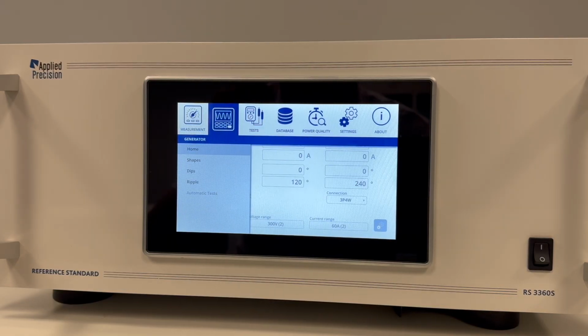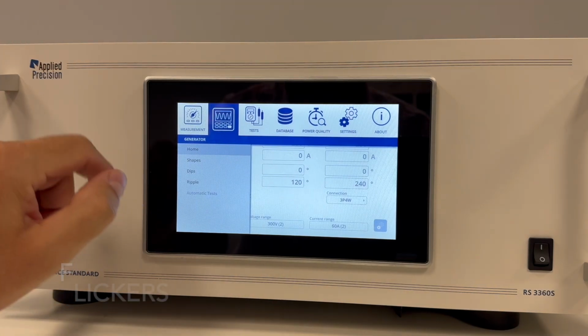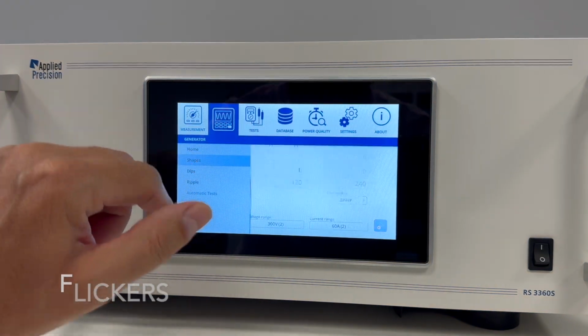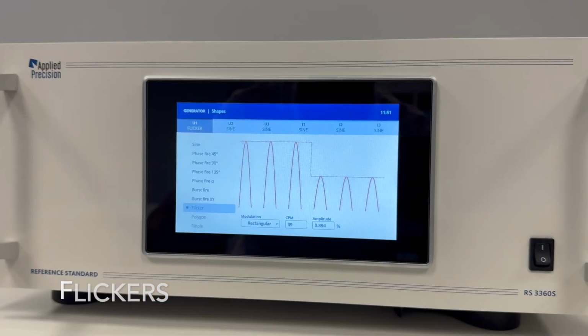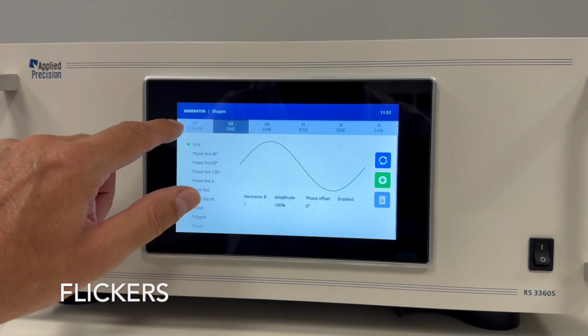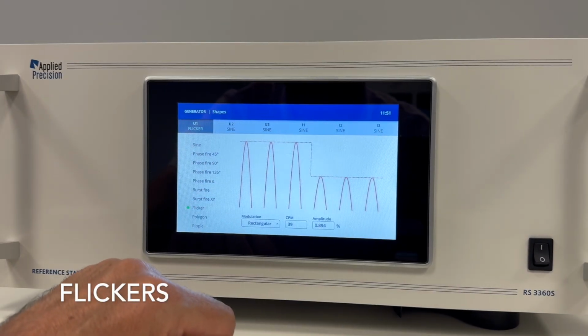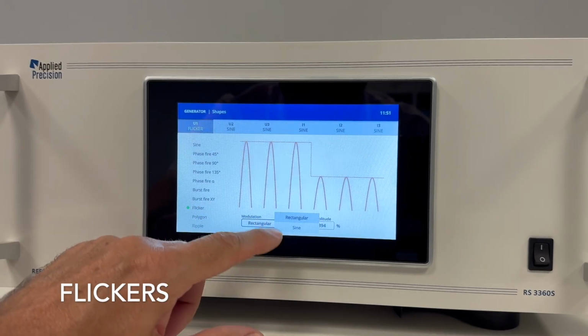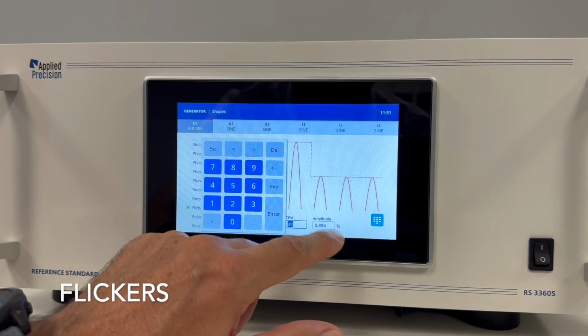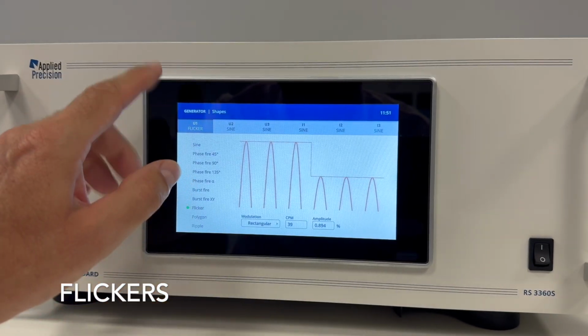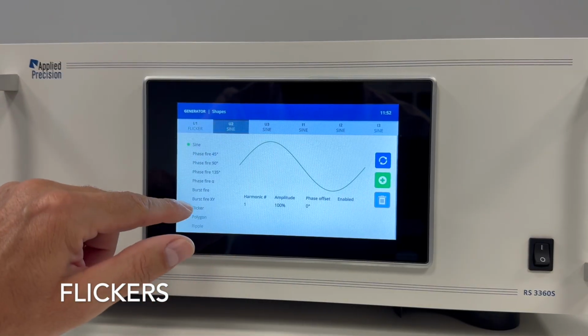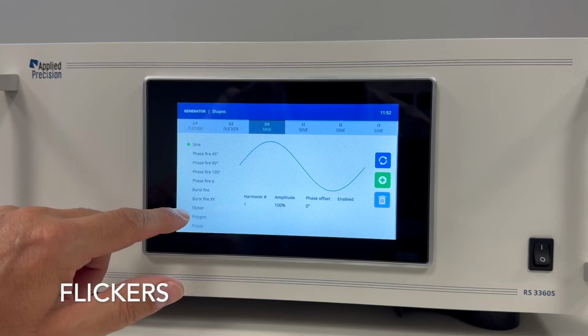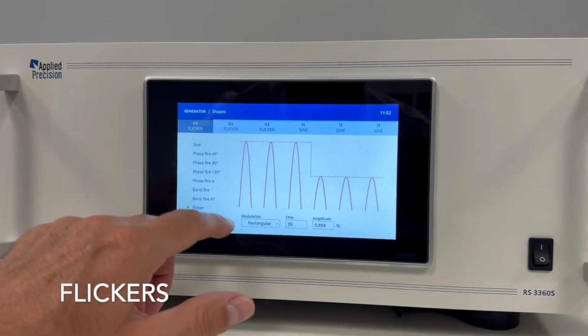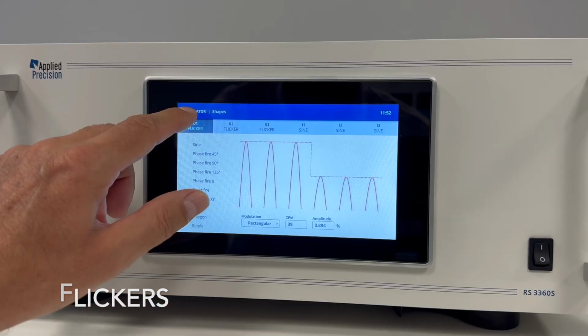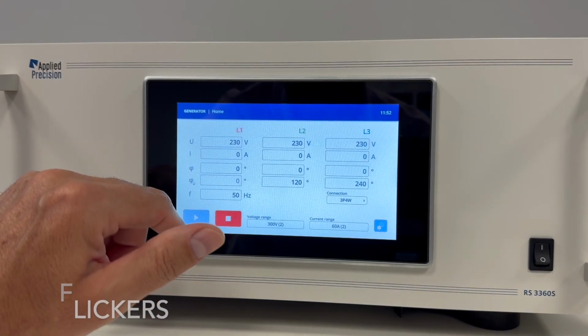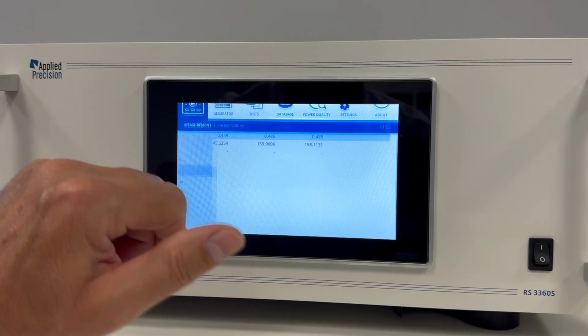In this section, let's focus on flicker. So we need to go again to the generator screen, shapes, flicker, and here we also have a predefined flicker for U1, for example. We can select the modulation shape, rectangular or sine, and other parameters here. So let's apply it to all three phases with exactly the same settings. This is as recommended by the standards. Let's go here, start it, and now let's check the measurement of the flicker values.